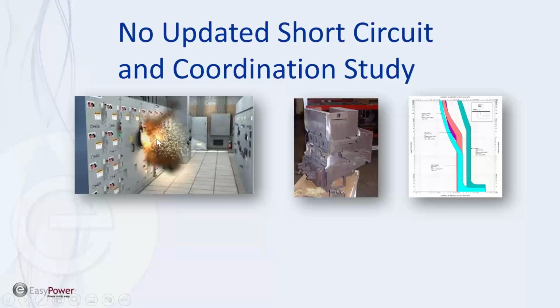It probably looked something like this when it happened. It blew the door off and so forth, but nobody was there when it happened, so thank goodness nobody got hurt. So if this was rated 75 or 85 or 100,000 amps, it would not have blown up. It would have just tripped the breaker and life goes on. You fix the problem, reset the breaker, and you're good to go. So that's the problem with overduty.